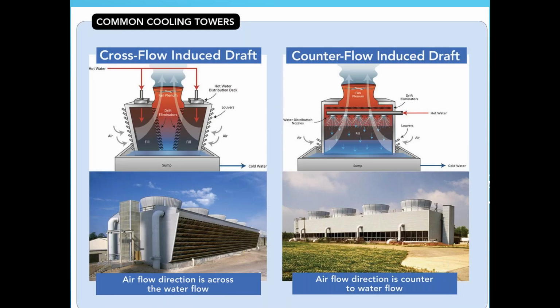The two most common fill direct cooling towers are the cross-flow induced draft, in which the airflow direction is across the water flow, and the counterflow induced draft, where the airflow direction is counter to the water flow. If we first take a look at the cross-flow, you can see it's easily recognized as the louvers go up the entire face of the tower for the whole longitudinal length.